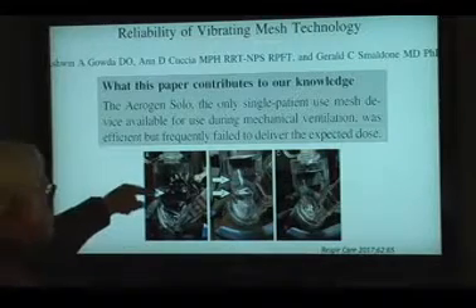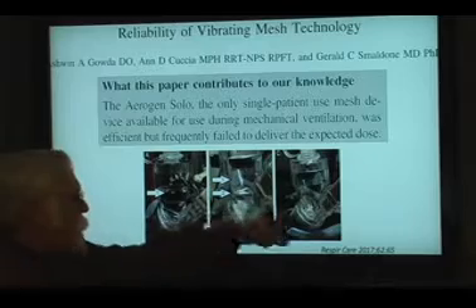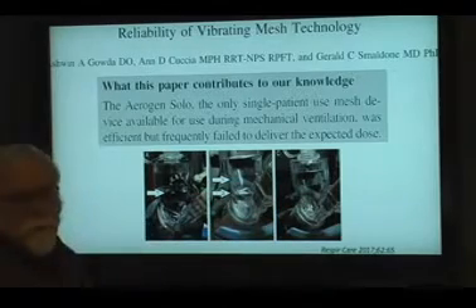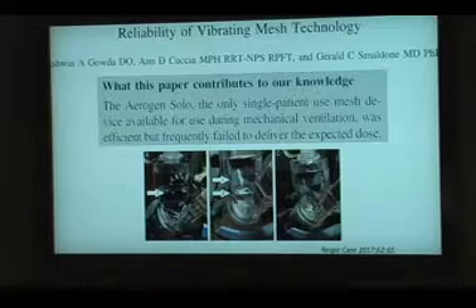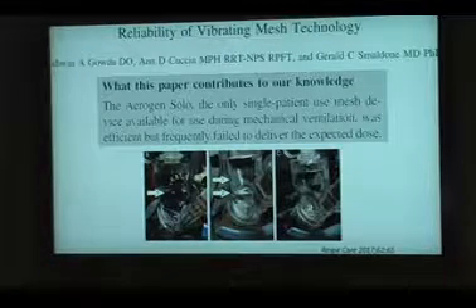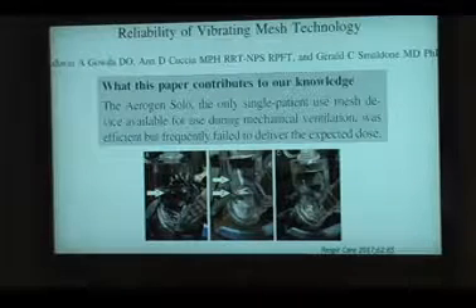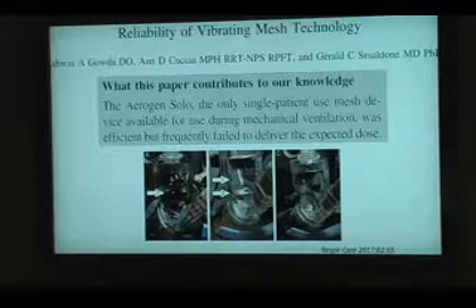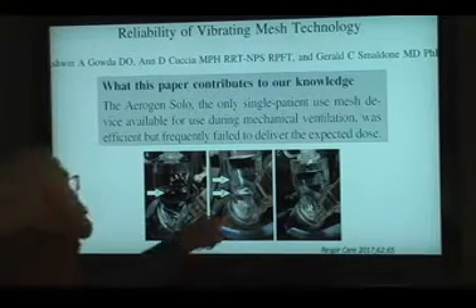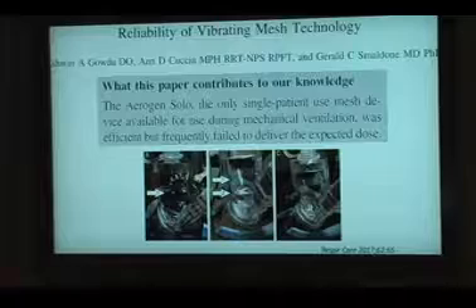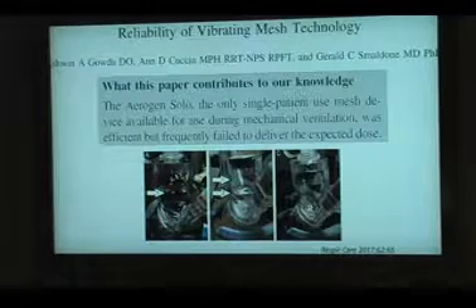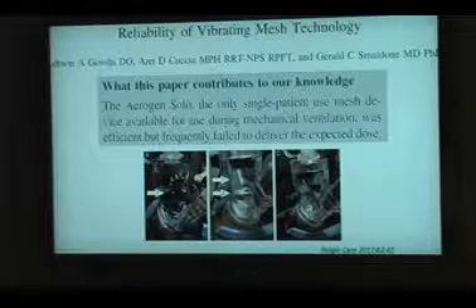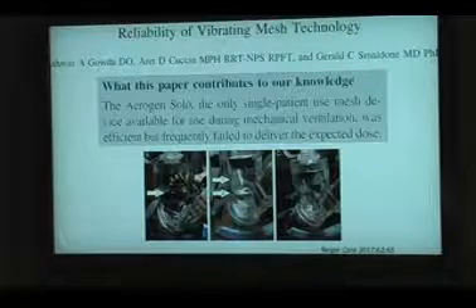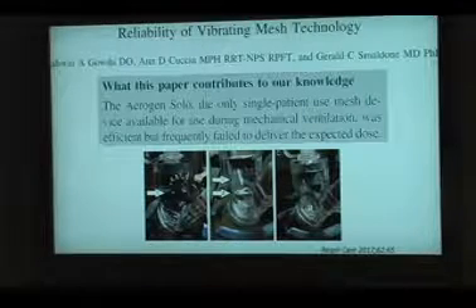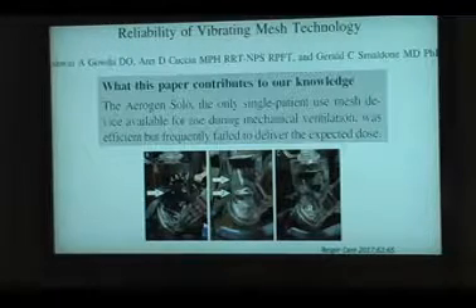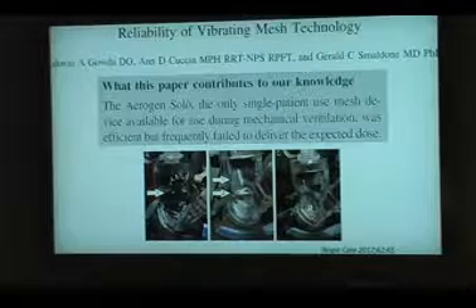So here it's filled. This one works great. All the liquid is gone. This one stopped. Just stopped halfway through the dose delivered. So what we found out, the reason for that is air bubbles on the surface. It appears. Yeah, especially so with the continuous. Maybe, I don't know if those are air bubbles there, but you can actually take that device, have it working, turn it so you get all the fluid off the mesh, and then turn it back up slowly, and it won't work. Click it, and it works again. This is for continuous. It shouldn't be that difficult.